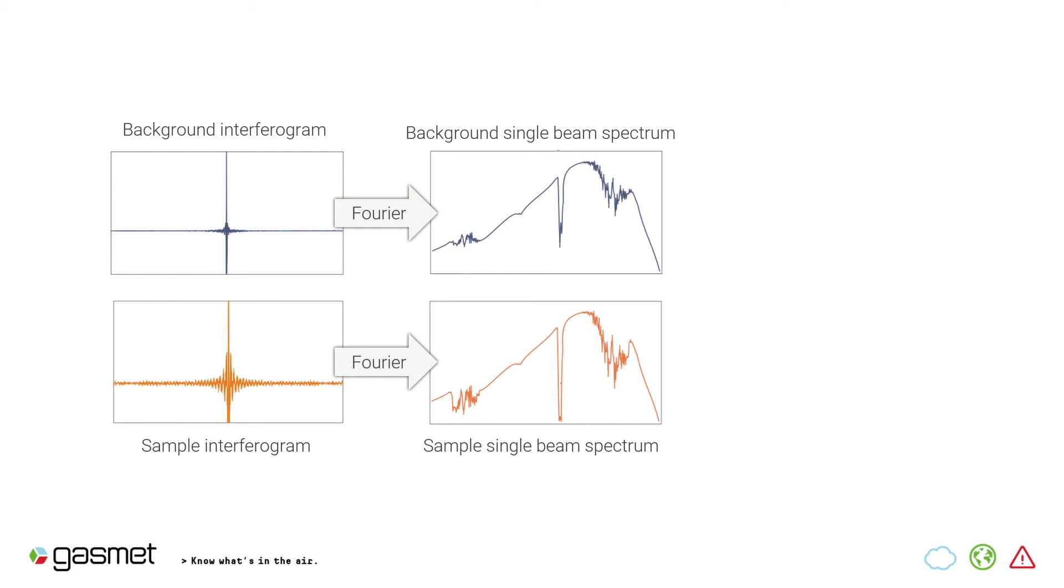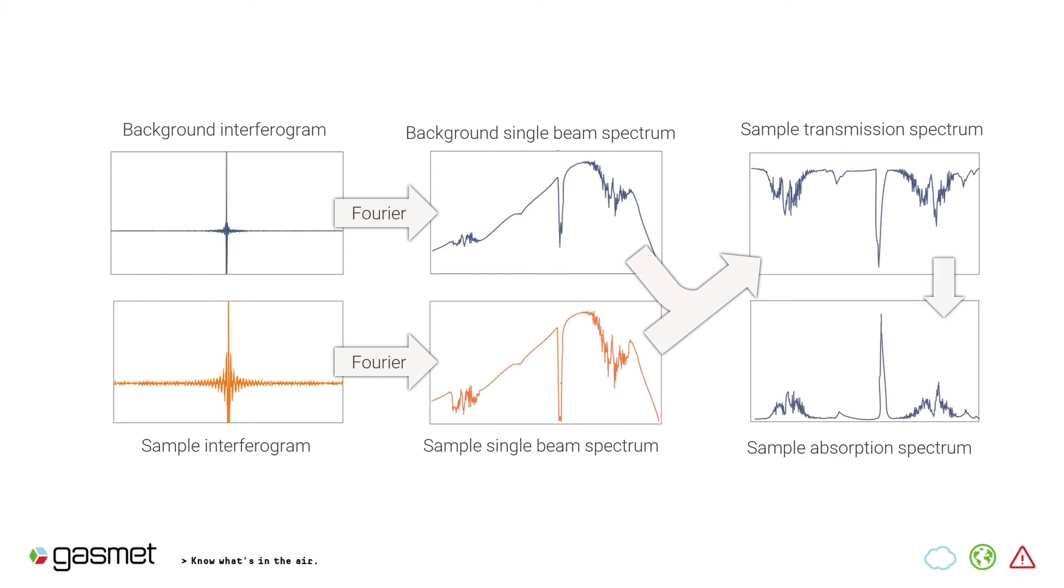Now, when we compare these two, we see what is the difference. So, how much of each wavelength went through the sample compared to the background? This is a transmission spectrum. This can be changed into telling us how much of each wavelength was absorbed by the sample. And this is an absorption spectrum. And these are what we use here in GASMET.